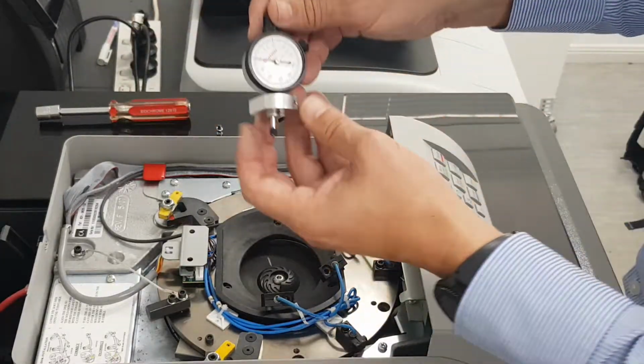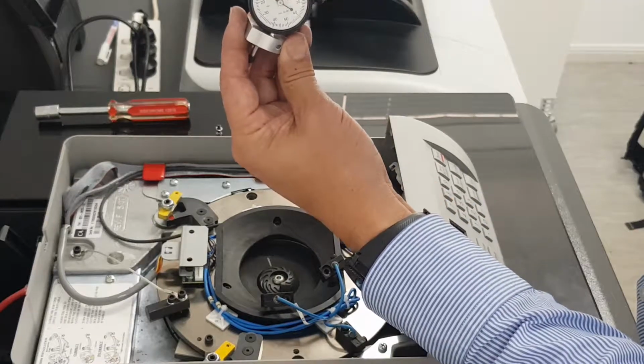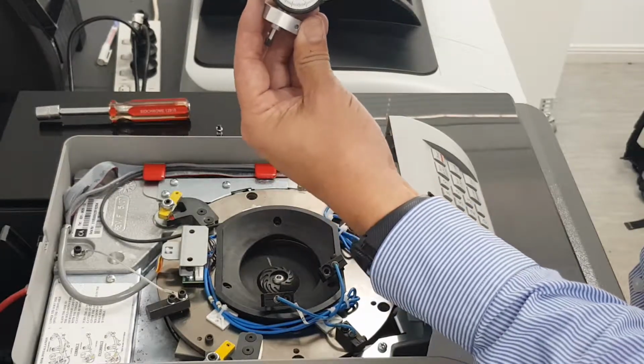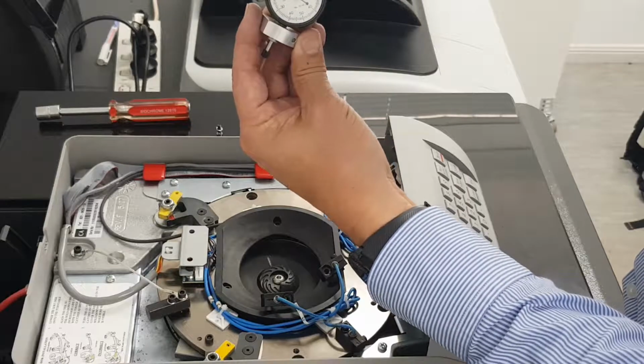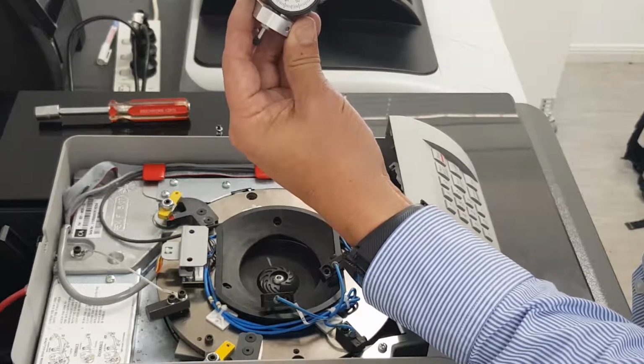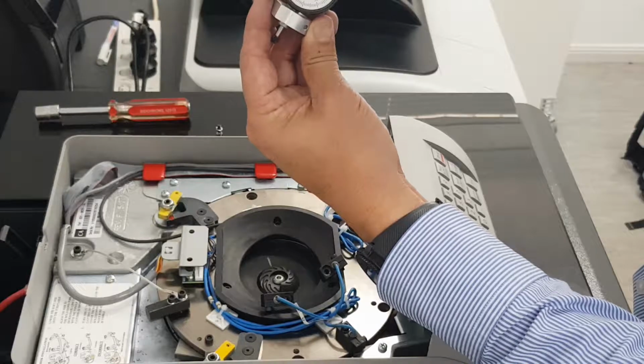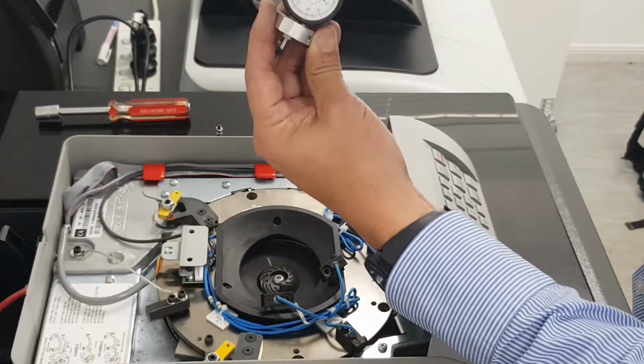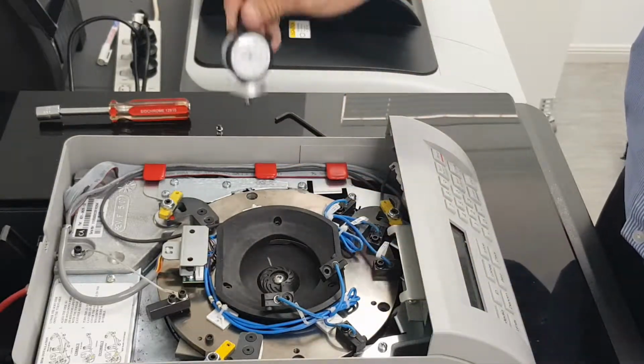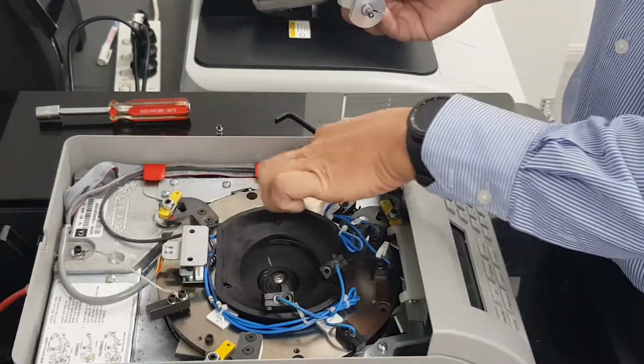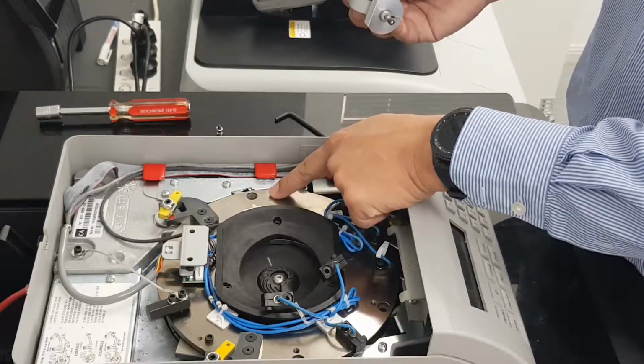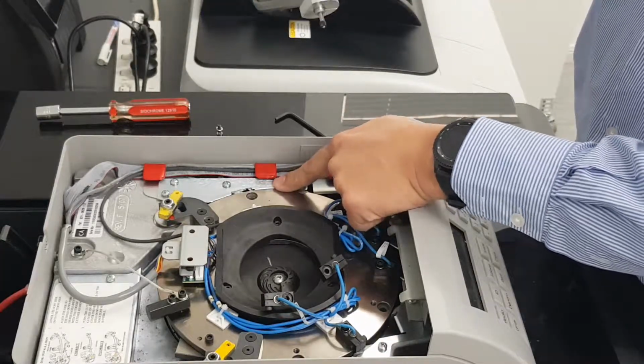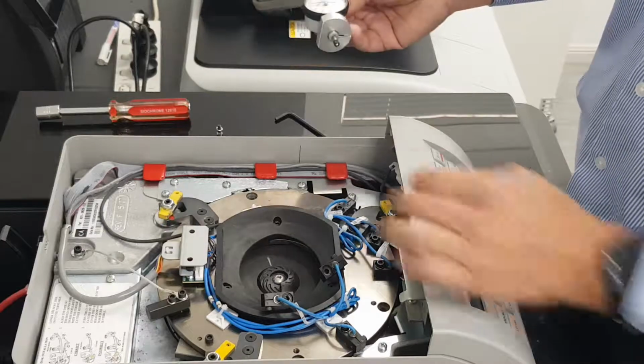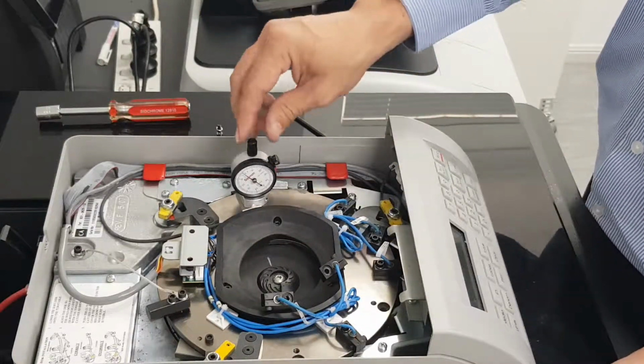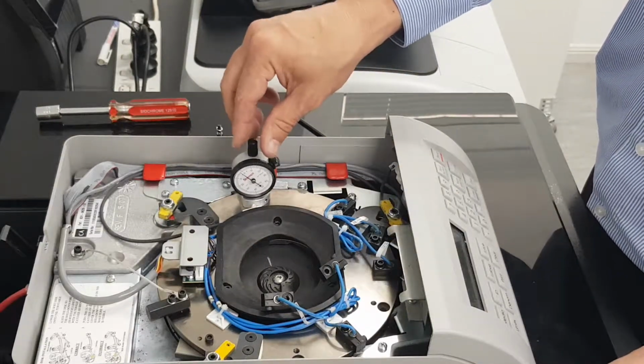Okay, so what we're looking for in our dial gauge, as you can see, there's our 0. Our reference point that we're going to be calibrating to is 0.002 of an inch, which is really only the second mark to the left of the 0, so it's a very fine adjustment. So from our first point, which is just there, we'll pop that in, and just make sure that this piece of metal on the side isn't sitting higher than the actual sort disc. Otherwise it's going to give you an uneven surface and it's really going to throw out your calibration. Okay, so you can pretty much tell when that's sitting on there if it's rocking at all.